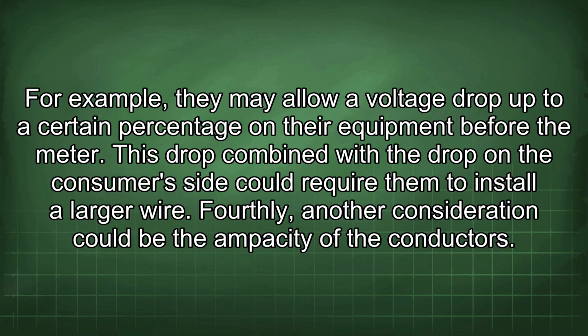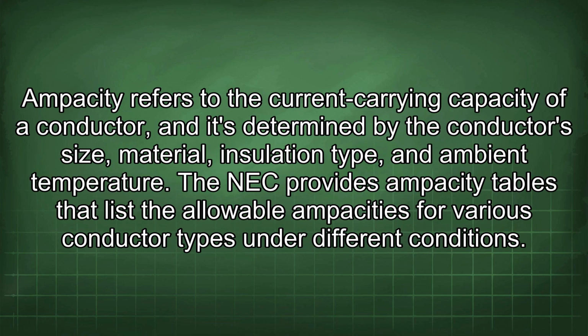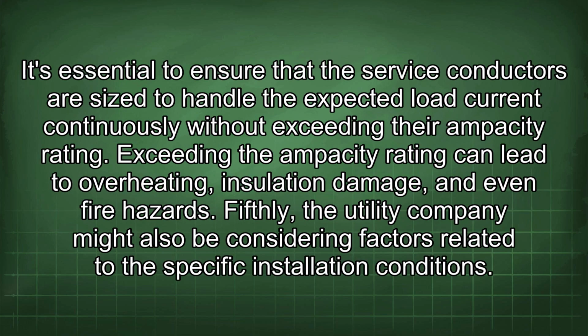Fourthly, another consideration could be the ampacity of the conductors. Ampacity refers to the current carrying capacity of a conductor, and it's determined by the conductor's size, material, insulation type, and ambient temperature. The NEC provides ampacity tables that list the allowable ampacities for various conductor types under different conditions. It's essential to ensure that the service conductors are sized to handle the expected load current continuously without exceeding their ampacity rating. Exceeding the ampacity rating can lead to overheating, insulation damage, and even fire hazards.